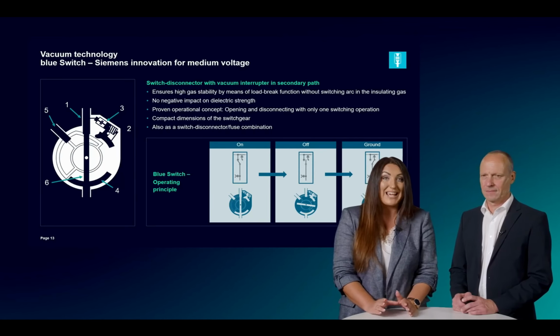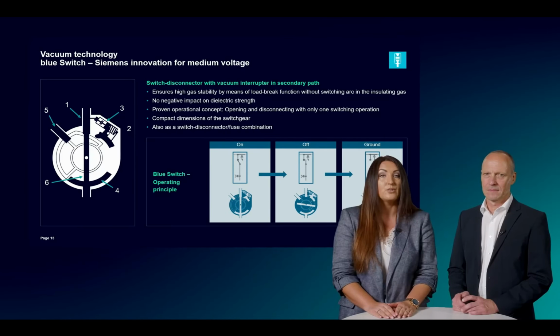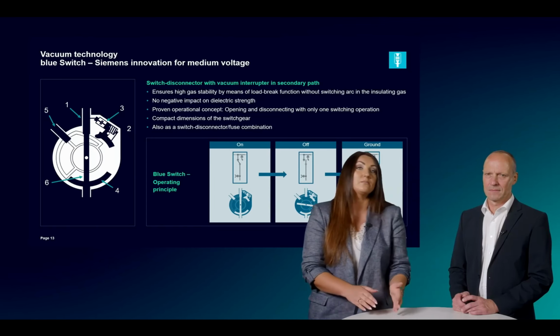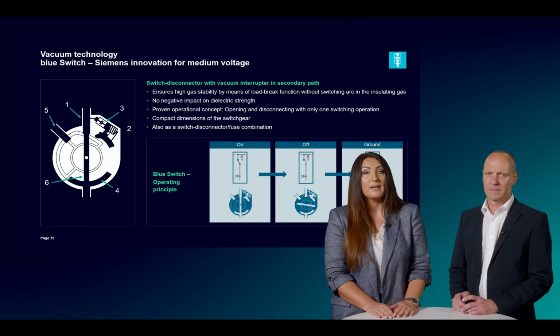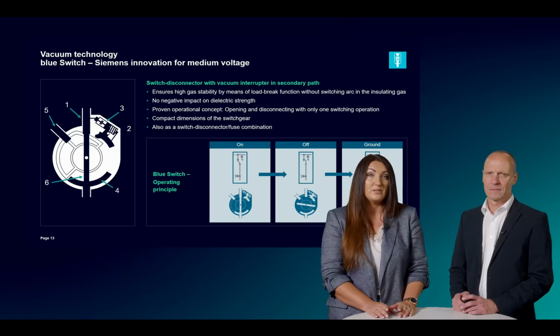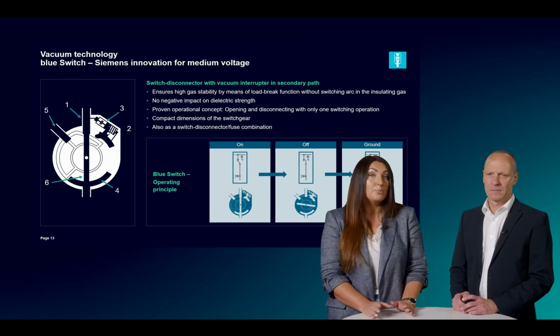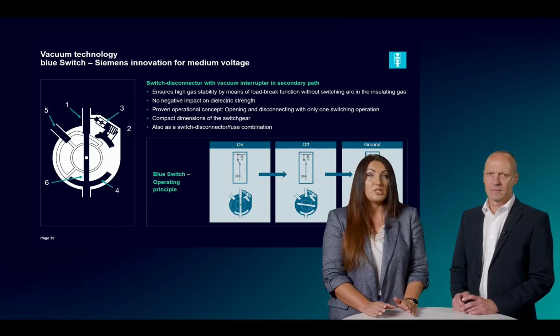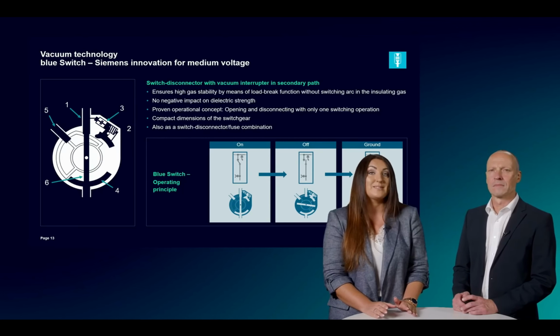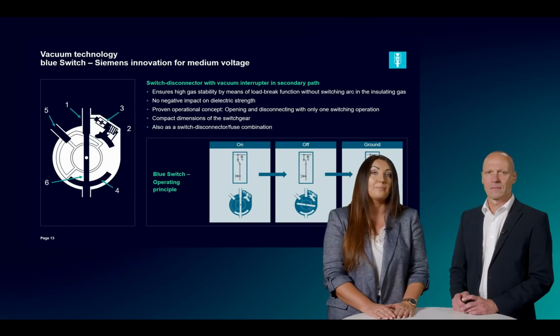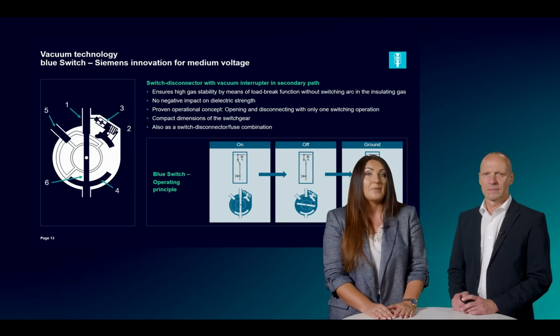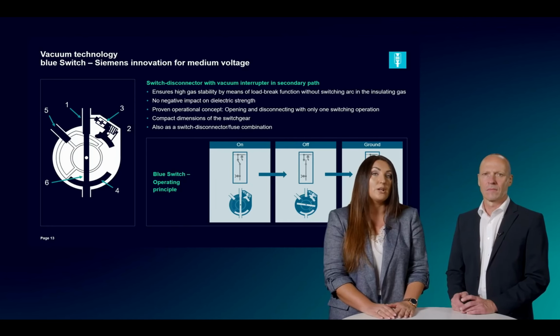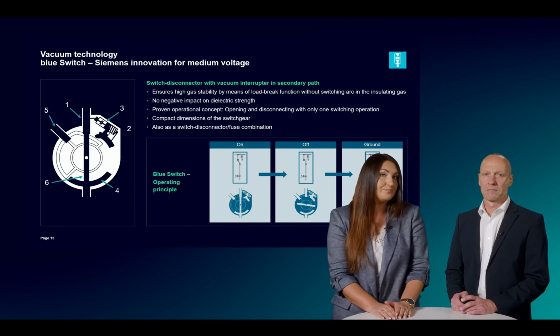And when the switch gets the off command, the current commutates via the moving switching blades from the busbar contact to the auxiliary contact. And in that way, it's redirected from the main path to the auxiliary path. When the blades reach the sufficient dielectric distance to the busbar contact, the vacuum interrupter opens and breaks the current. So during the short time which is needed for the current breaking, the switching blades still slide across the auxiliary contact and prevent any arcing in the gas compartment. And then they move further, leaving the auxiliary contact without the current, and ultimately also reach the off position.